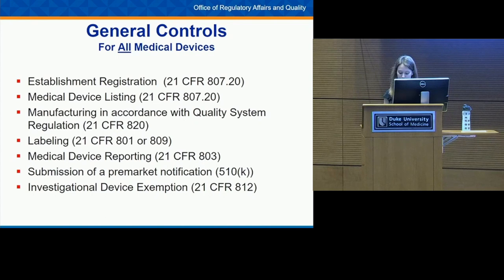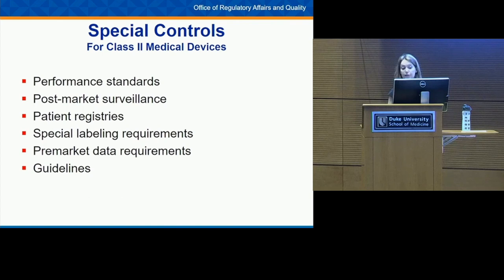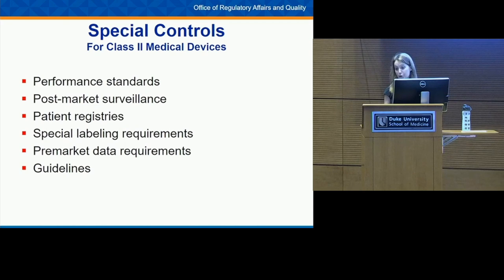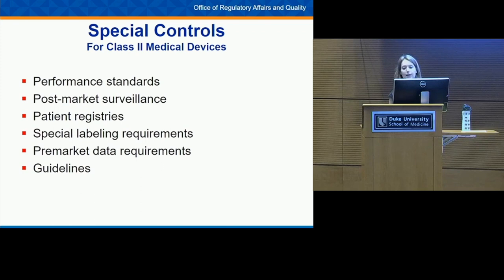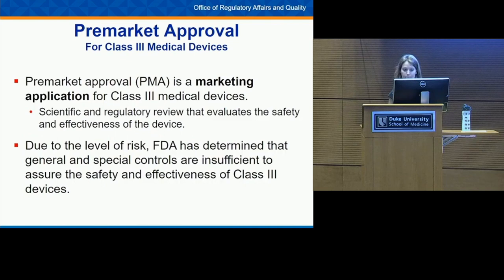Special controls are specifically required for Class II devices and are more tailored to the specific device. They may include performance standards — for example, a blood pressure cuff must pass specific accuracy tests. There may also be post-market surveillance studies (required when device failure would be serious, or for pediatric populations or implants), patient registry requirements to track outcome data, special labeling requirements, and other pre-market data requirements, all dictated by the specific device being developed.